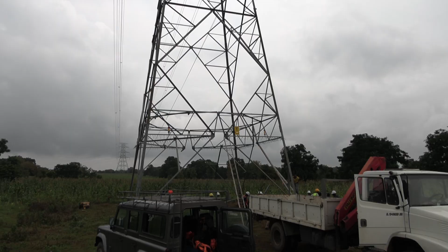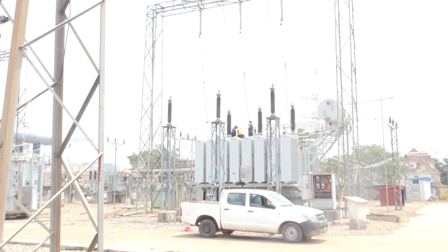Routine inspection and maintenance is not limited to transmission lines, but is also carried out in 330 and 132 kV transmission substations. Routine servicing includes transformer inspections, testing of protection systems, servicing circuit breakers, checking relay panels, and monitoring switchgear performance.